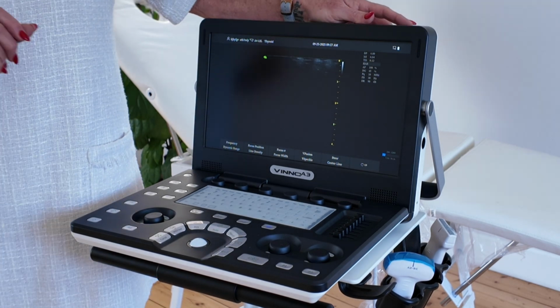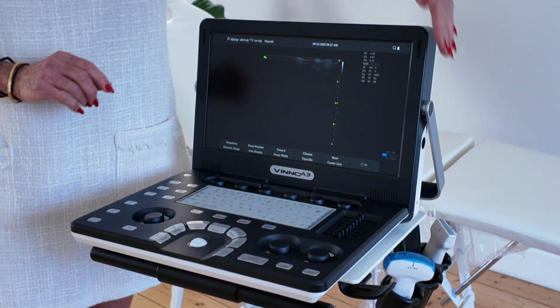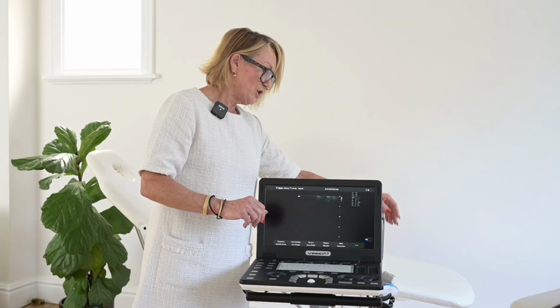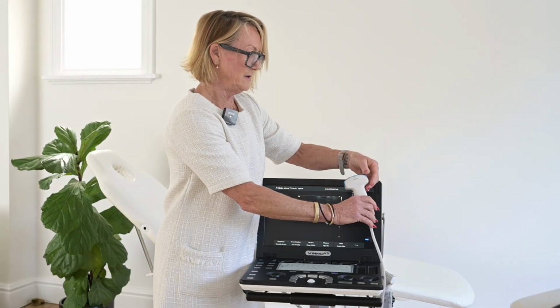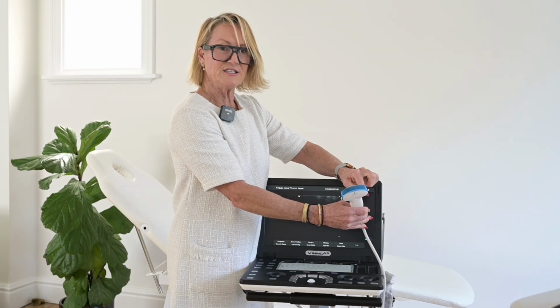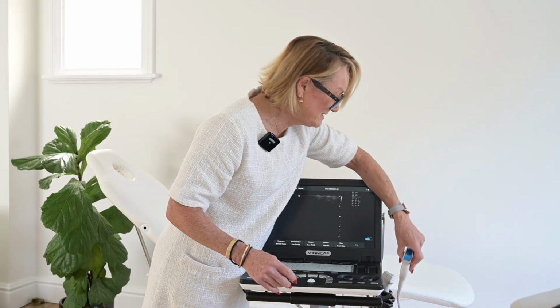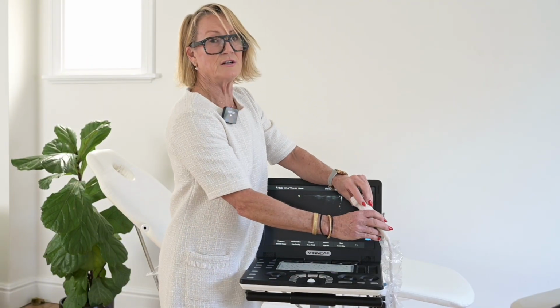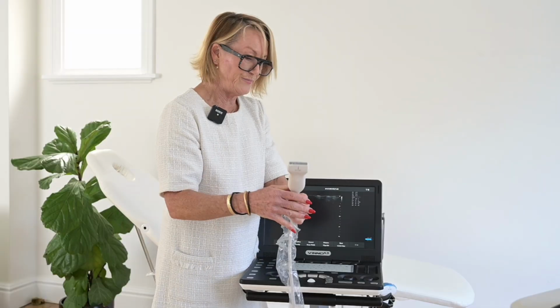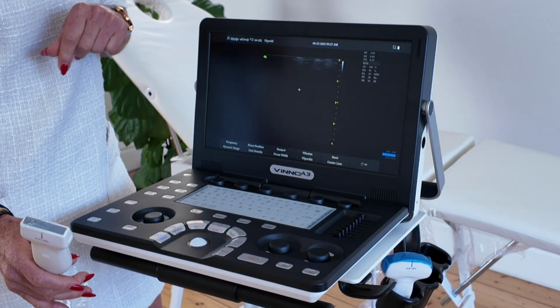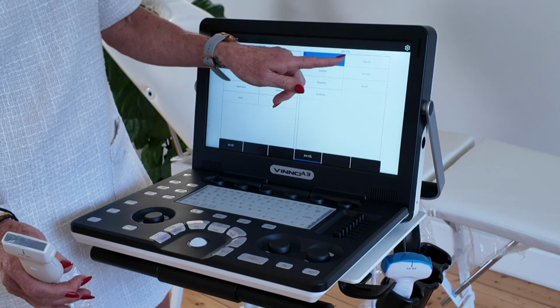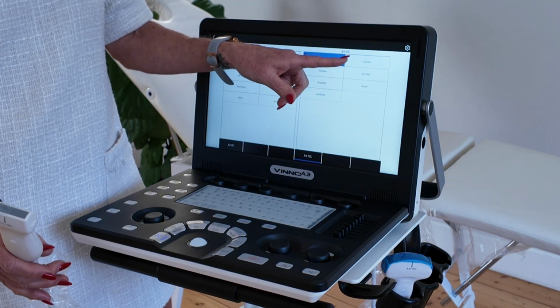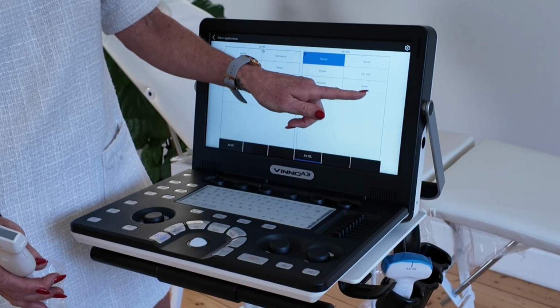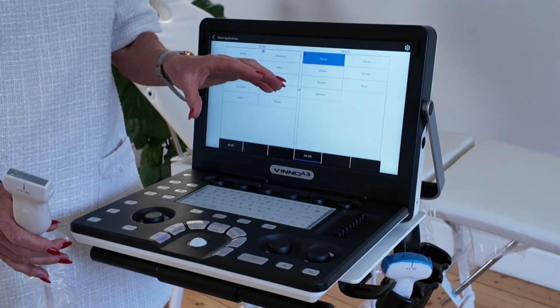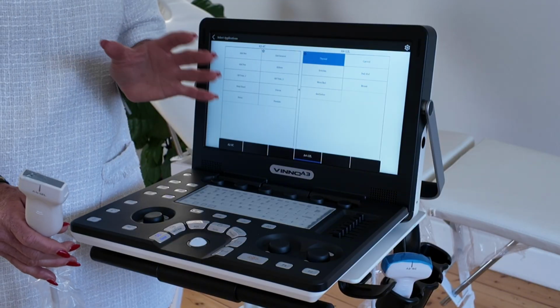What we do next is we move to this probe selection. So on this system you have two types of probes. You have this one with the curved type of interface, which is called a convex probe. Lower frequency gets to deeper areas. The next probe that you use specifically in musculoskeletal ultrasound and aesthetics is the linear probe. This is the one.